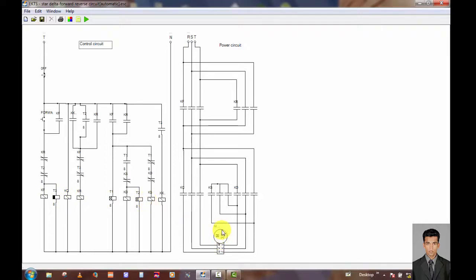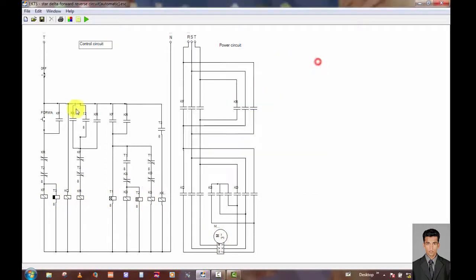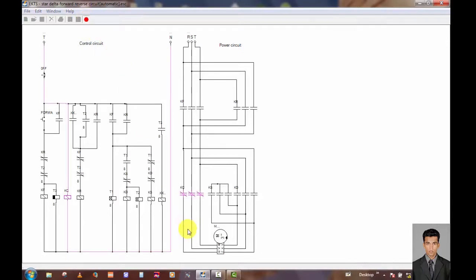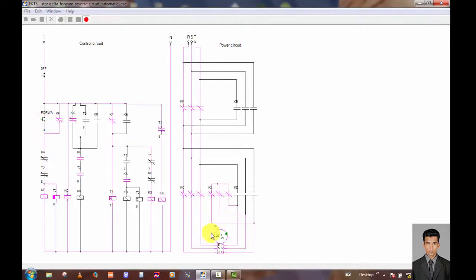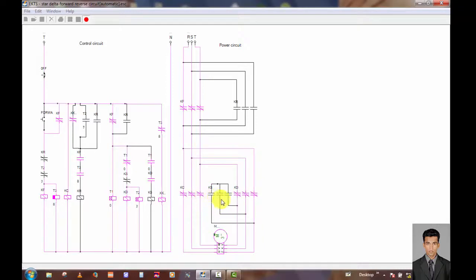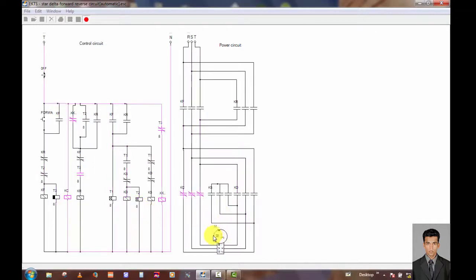This is a 3-phase motor. Now I energize this control circuit and power circuit using this run button. You can push this button and you can see the motor rotate. This timer is timing from 1 to 8, and it is transferred from Star to Delta.